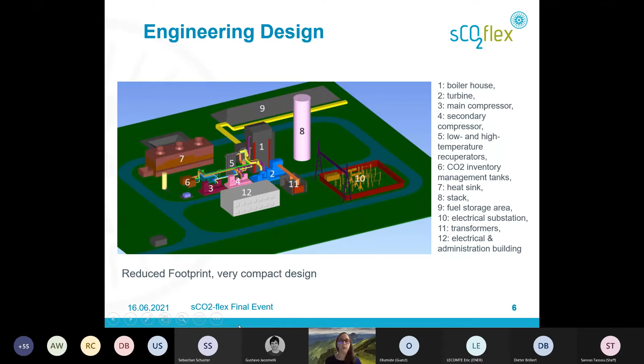We also worked a lot on the flexibility and to understand the operation of the cycle. So the plant operation was, as I say, with a really new strategy. In order to understand the off design and to be able to model the dynamic performance of the cycle, we tested several operating strategies, and we chose one which mixes different strategies. First, we have a sliding pressure for the turbomachinery, which is a current strategy in an actual plant. We also have some variable speed fans for the heat rejection unit. And we work with a supercritical CO2 inventory in order to set the cycle minimum pressure.